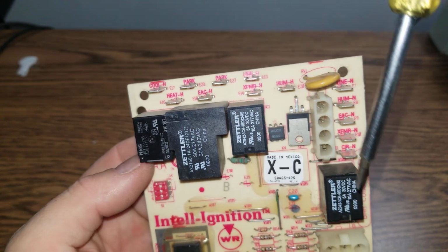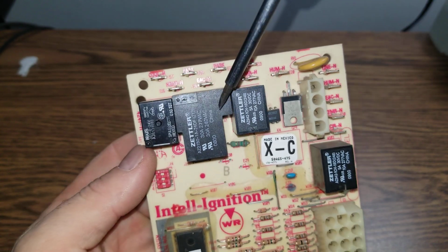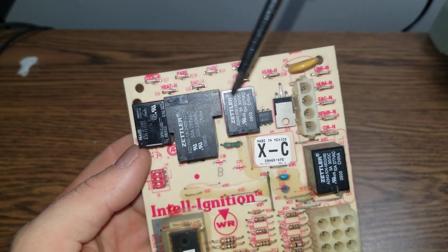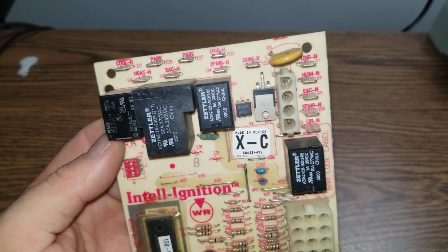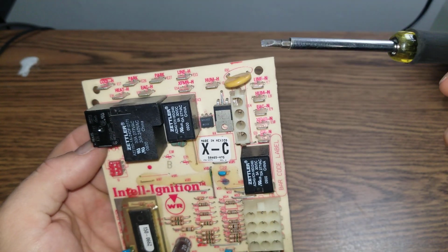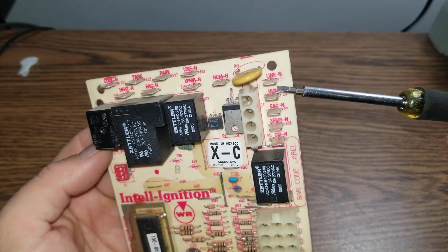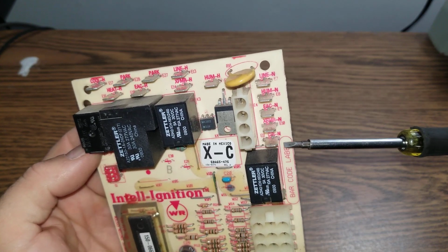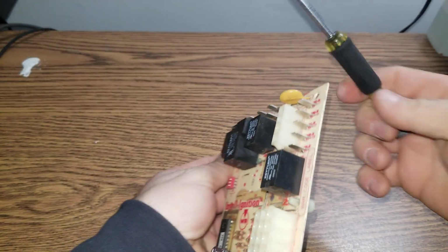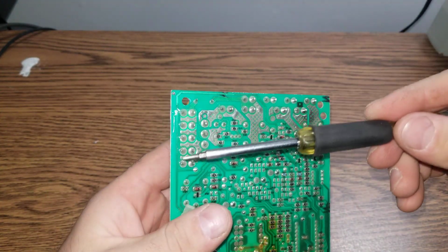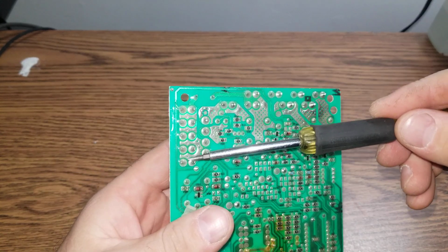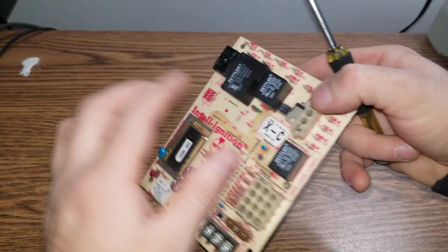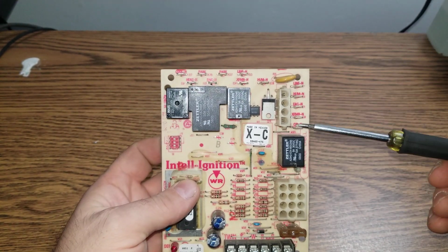Well, I don't know which relay is for what function, but we know that this is a blower relay. And the others can be inducer, can be a hot surface igniter, and so on. On this side, it says neutral, neutral, neutral, neutral, and neutral. So all these are neutrals. We can find here that they are all connected. So they are all neutral connections. So we basically simplified up to here.